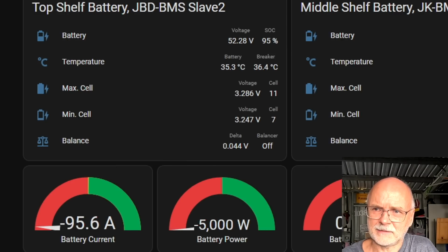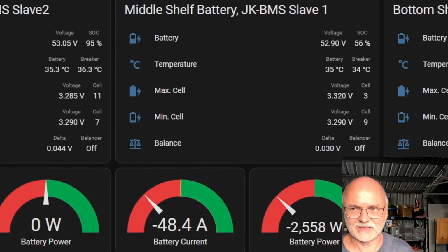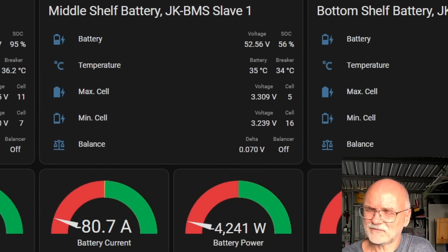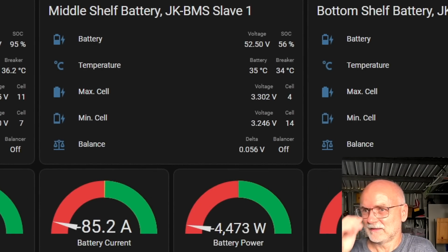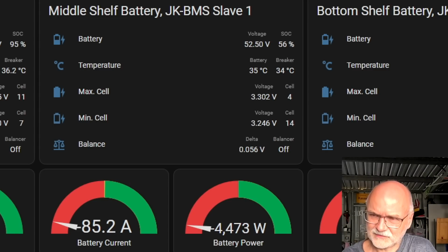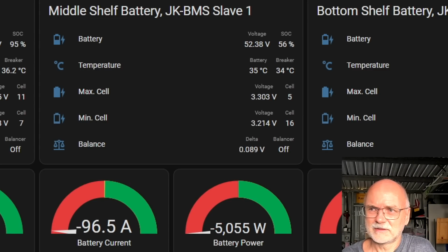At 100 amps, at 5 kilowatt now, we are seeing 44 millivolt. Okay, middle shelf battery again. Hey, look at this, 70 millivolt deviation already. At 4.4, let's see if we get 5 kilowatt here as well. There we go, 5 kilowatt, 90 millivolt deviation. I think this is too high, right? It is too high, and it's cell number 16, that's the main positive.